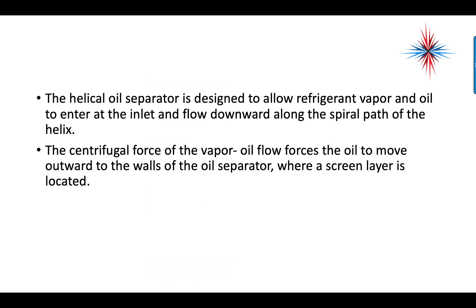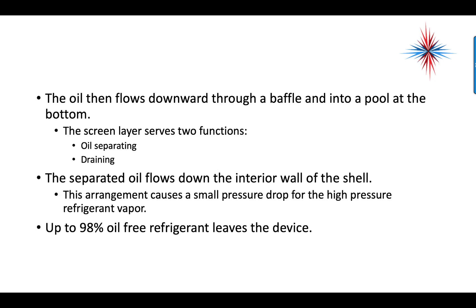The helical oil separator is designed to allow refrigerant vapor and oil to enter at the inlet and flow downward along a spiral path of the helix. The centrifugal force of the vapor-oil flow forces the oil to move outward to the wall of the oil separator where a screen layer is located. The oil then flows downward through a baffle into a pool at the bottom. The screen layer helps separate the oil as it goes around the helix and allows draining as oil molecules and droplets drain down the screen. Helical oil separators allow 98% oil-free refrigerant to leave the device.